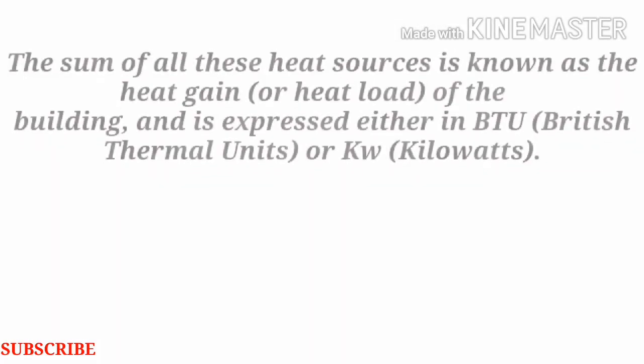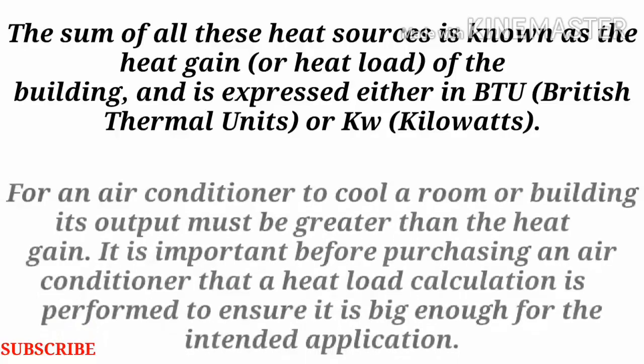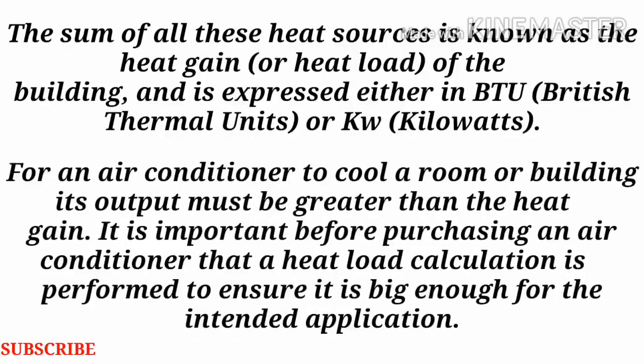The sum of all these heat sources is known as the heat gain, or heat load, of the building, and is expressed either in BTU (British Thermal Units) or kW (kilowatts). For an air conditioner to cool a room or building, its output must be greater than the heat gain. It is important before purchasing an air conditioner that a heat load calculation is performed to ensure it is big enough for the intended application.